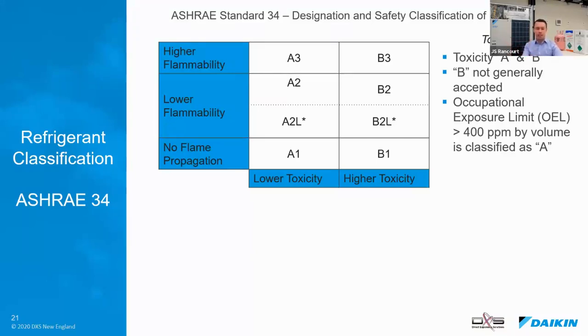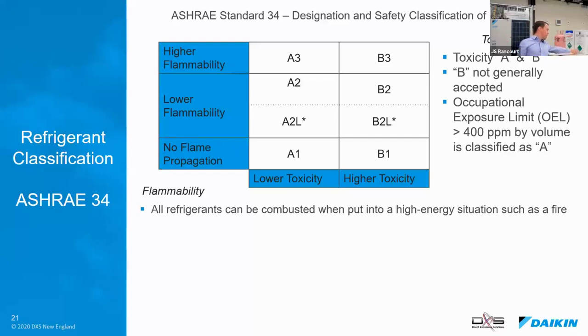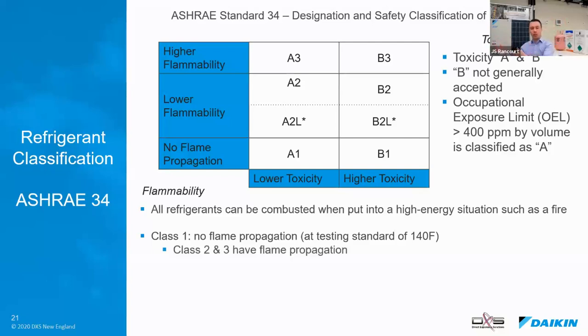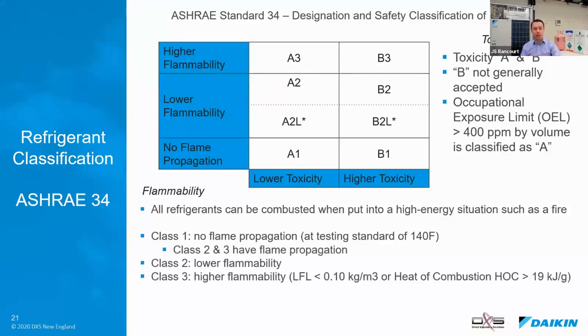Now, the hot topic these days, no pun intended, is flammability. So essentially, one thing to note is even though these refrigerants have a non-flammable logo on them, all refrigerants can essentially be combusted. All refrigerants that we use can essentially be combusted if they're put into a high energy situation. If this building was to get on fire, any refrigerant in here would eventually combust. However, a class one refrigerant, there's class one, two, and three. A class one refrigerant means it has no flame propagation when tested at 140 degrees Fahrenheit. Class two and three refrigerants do get some amount of flame propagation.